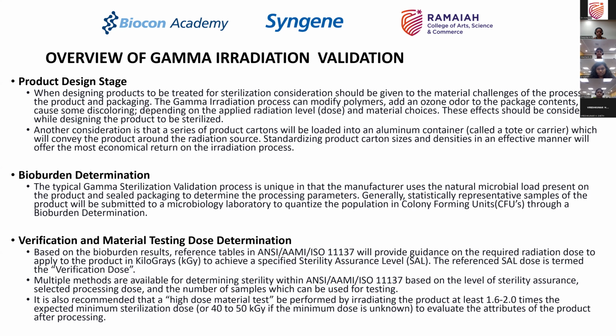Now, if that dose is not known, if for any reason the table does not provide you the dose, then you assume 25 kilograys as the base dose, and then for the high dose material test you use 40 to 50 kilograys because you don't know the minimum dose, so that you can know what the effect is if you expose it to a higher dose. So it's like a bracketing approach where you are saying that I will not go above this, I will not go below this, this is where my optimum study is.